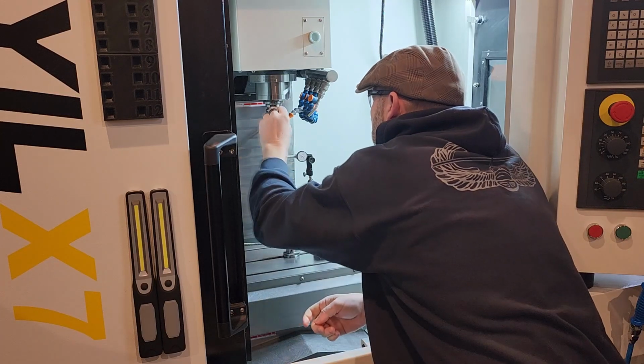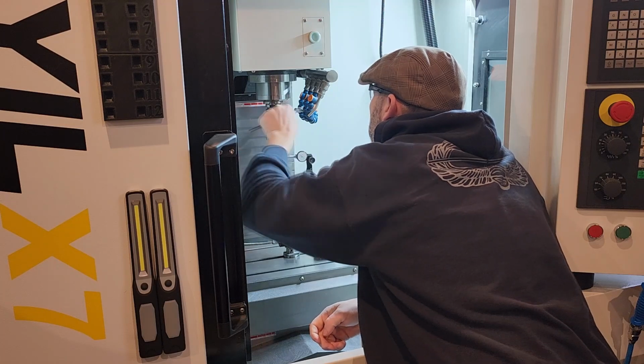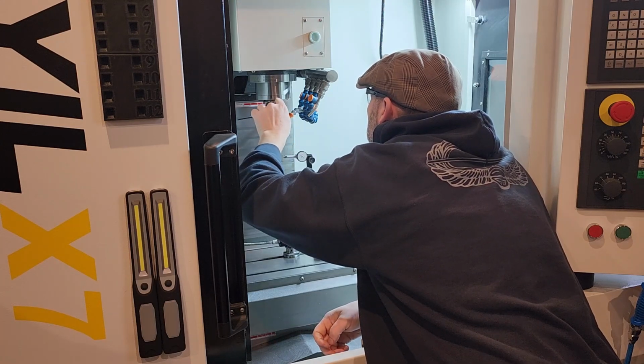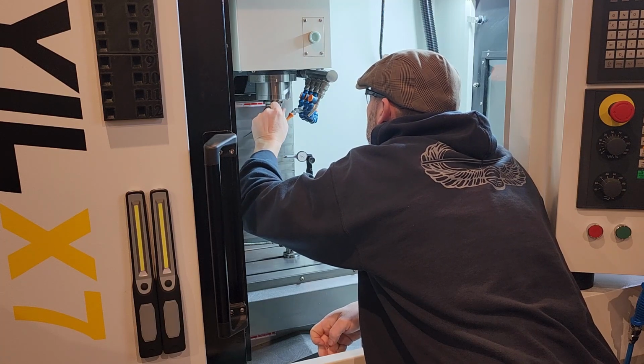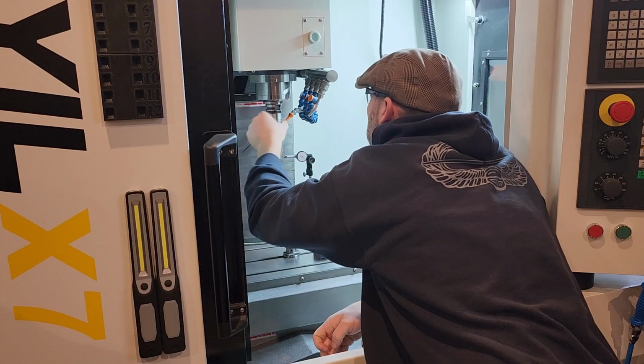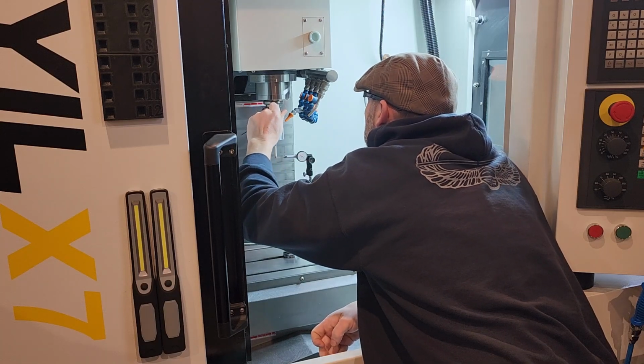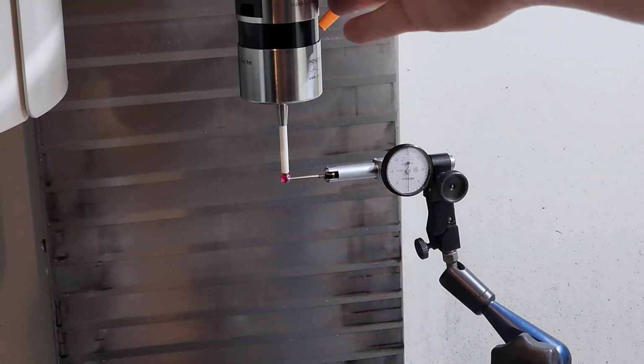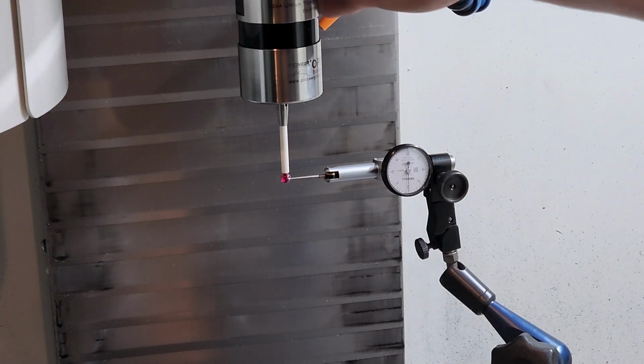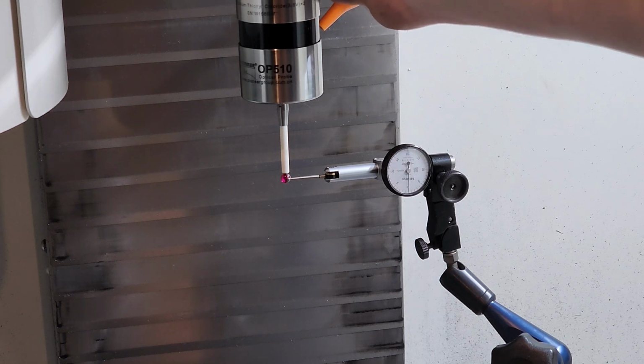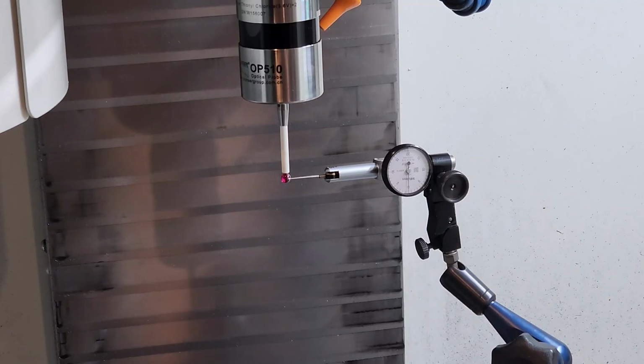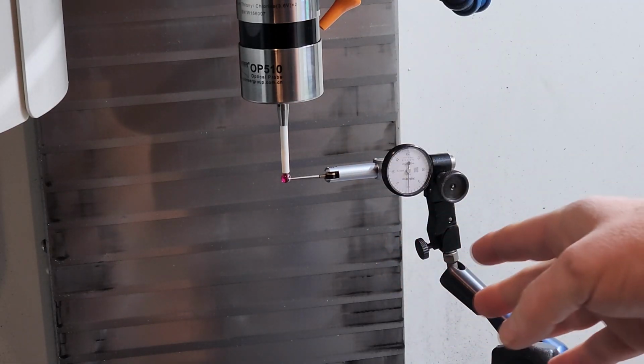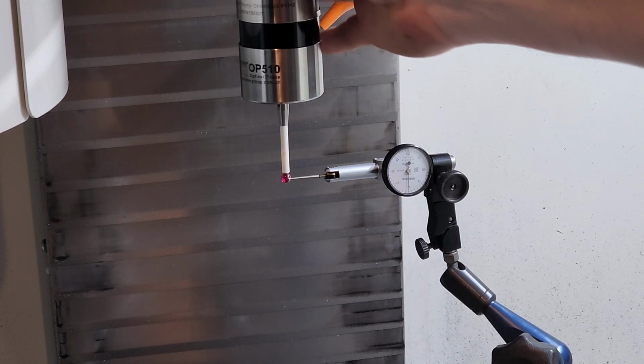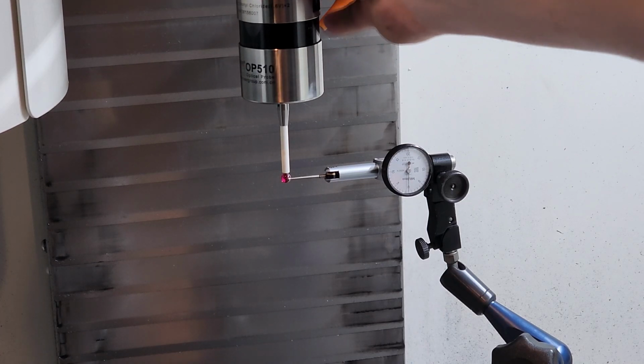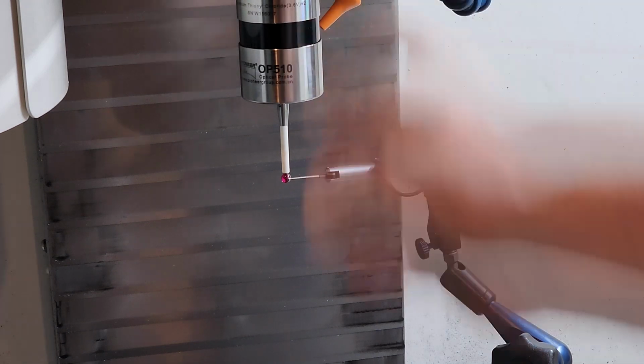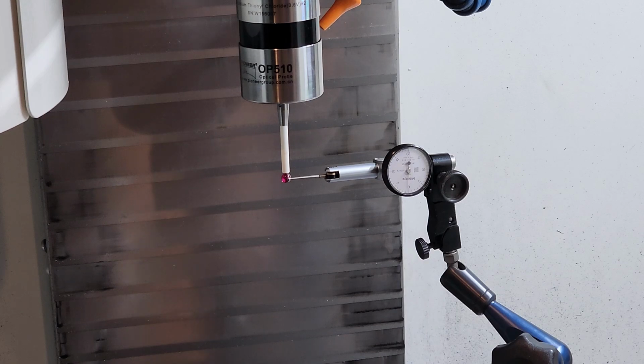After working on it for about 20 minutes, I now have it dialed into a bit more than 1/10,000th of an inch, about 0.0002 to 0.0003 inches. Unfortunately, this does not meet the 0.003 millimeters specification. Currently, the run out is approximately 0.005 to 0.007 millimeters. If I can't further improve the run out, I can expect less accuracy and worsen the repeatability. However, there will always be some irregularities with a probe's setup and physical characteristics. I have to assume that part of the point of the calibration routines is to compensate and adjust for these irregularities.